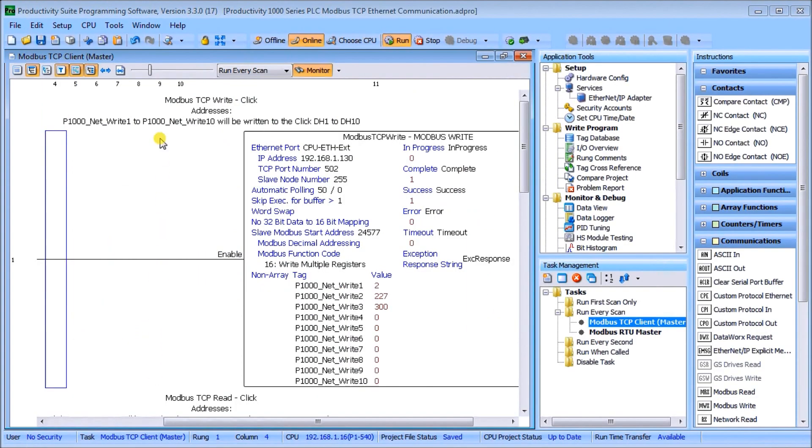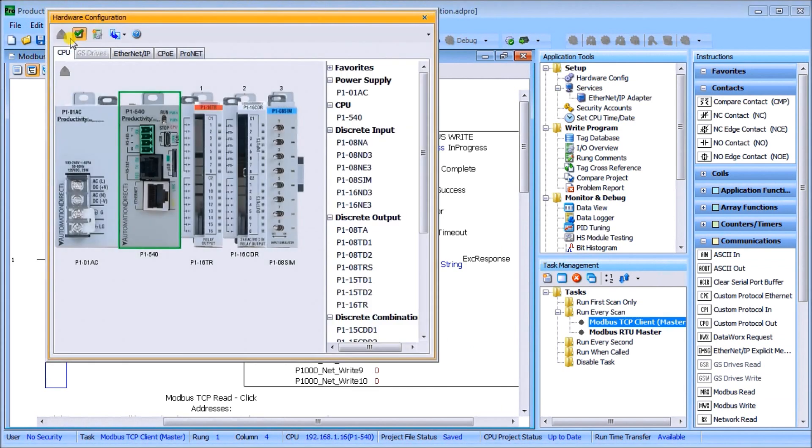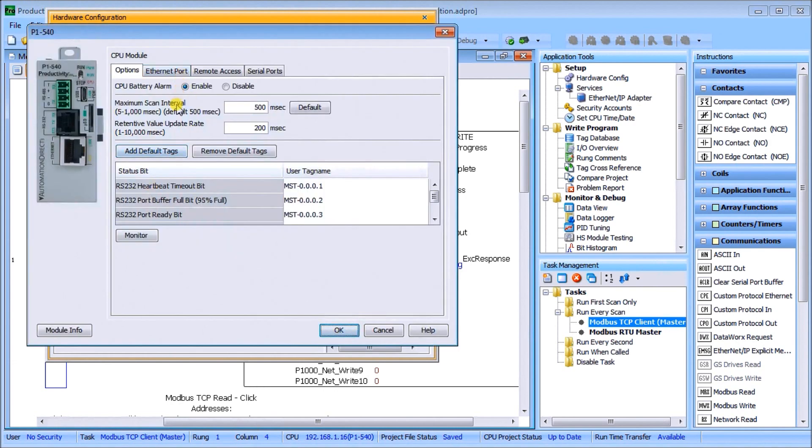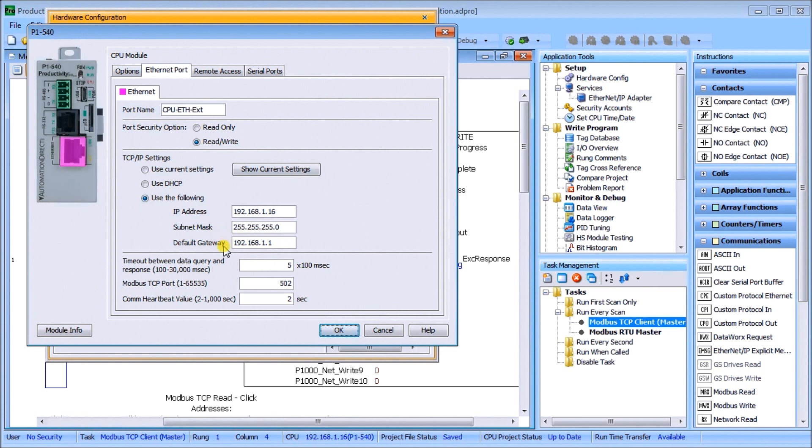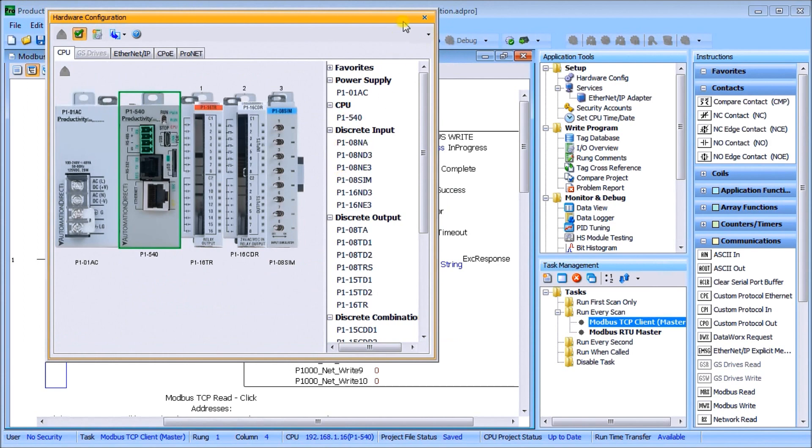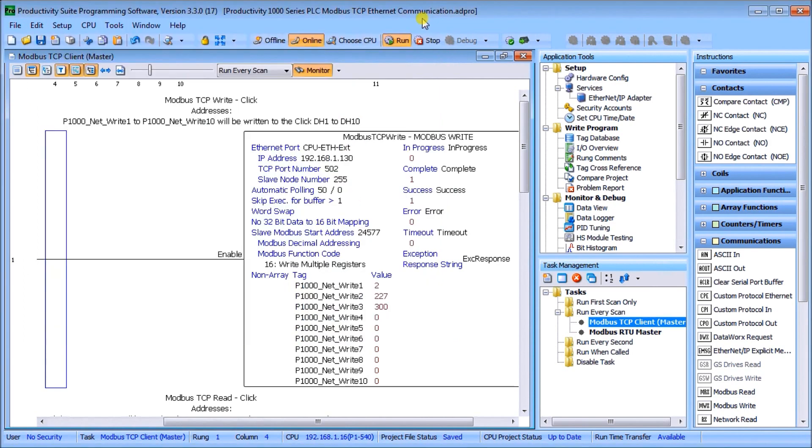To verify under Setup, we have our Hardware Configuration. We can click on our CPU here and then look at our Ethernet port. This gives us our IP address for Ethernet, which is 192.168.1.16. We have our subnet mask which is the same, we put a default gateway in here which connects us to our intranet, and we have our Modbus TCP port set for 502. Everything else is the default. That's where the information actually comes from.